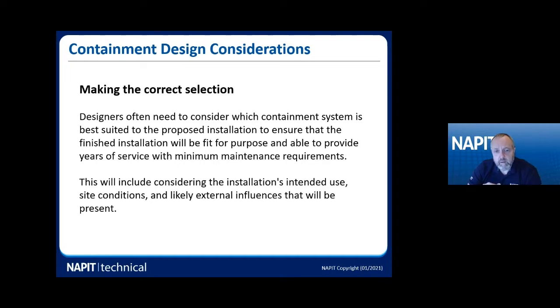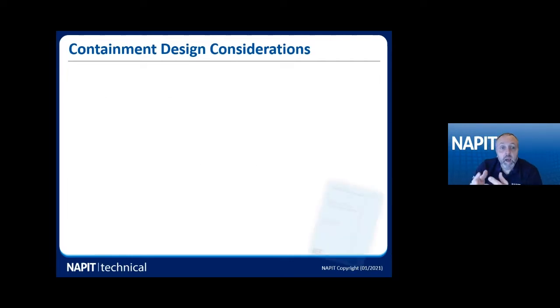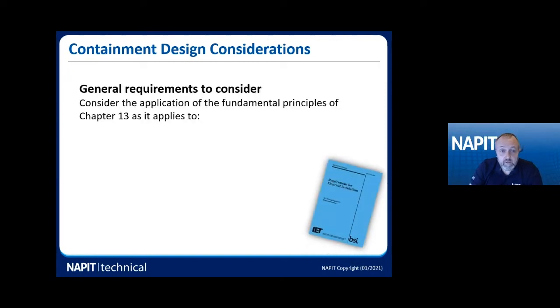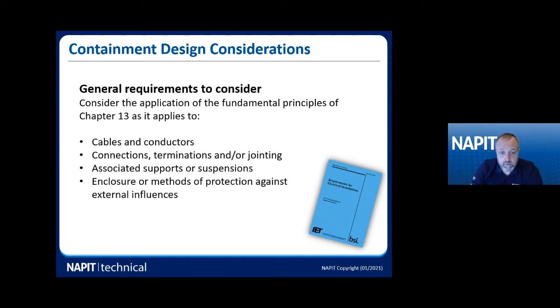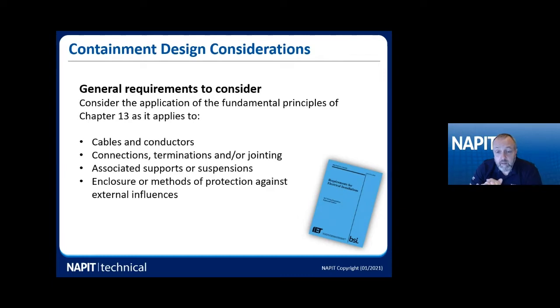Above all else, when we look at our containment we've got to think about external influences that could possibly be present. Chapter 13 asks us to look at cables and conductors, connections, terminations, any jointing, associated supports and suspensions. That's quite important when we're putting together large pieces of tray, basket, or trunking overhead, because if we have too big a gap between supports or haven't anchored our drop rods into a suitable substrate, we could be in a lot of problems — especially if we're overloading our tray with too heavy a cable.